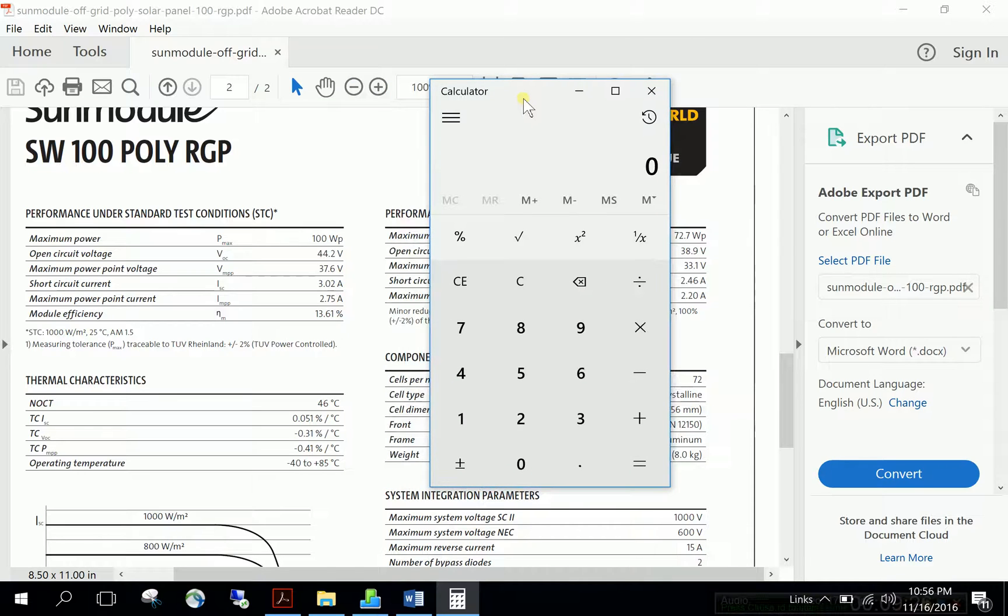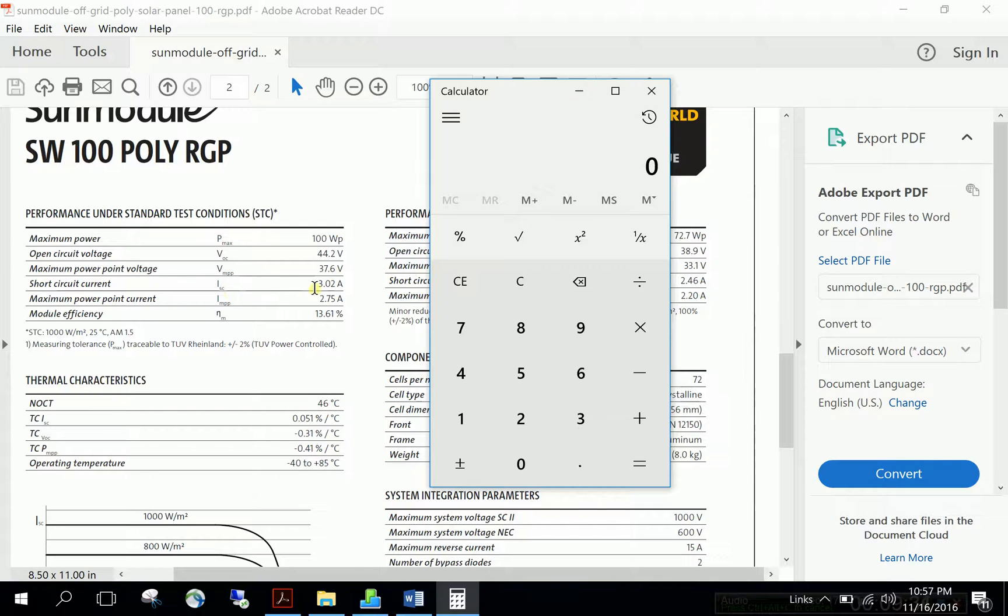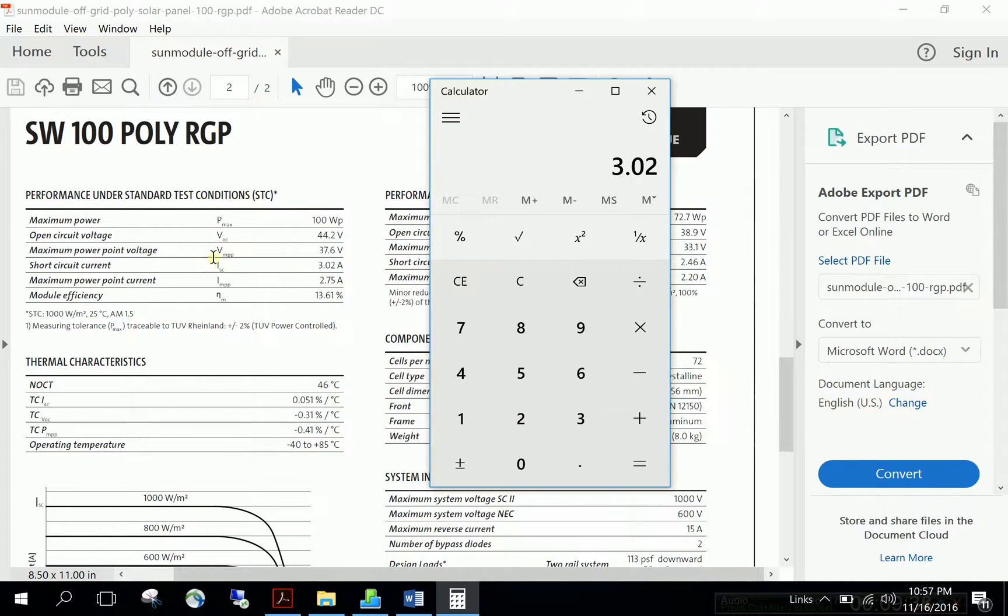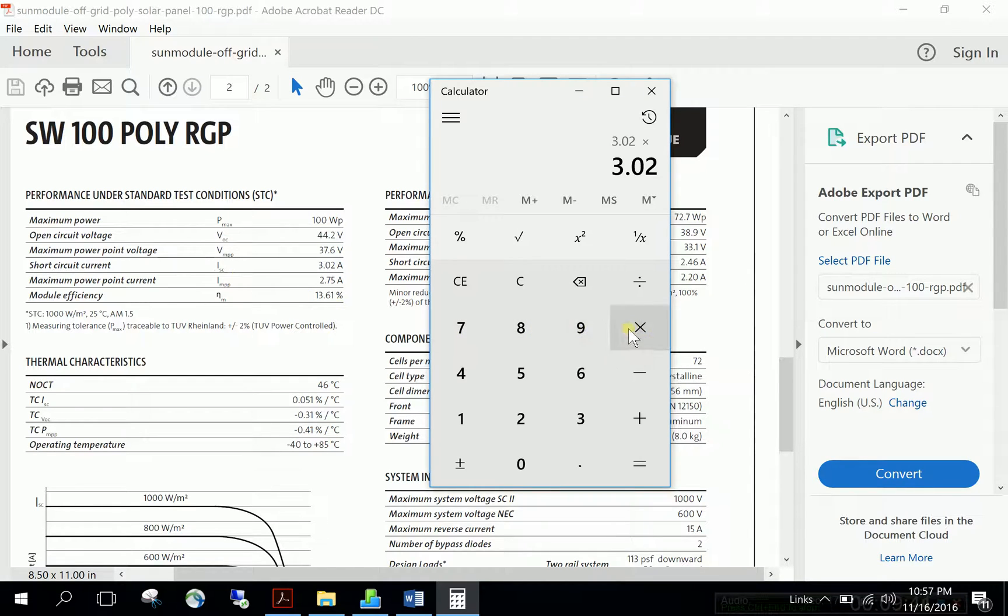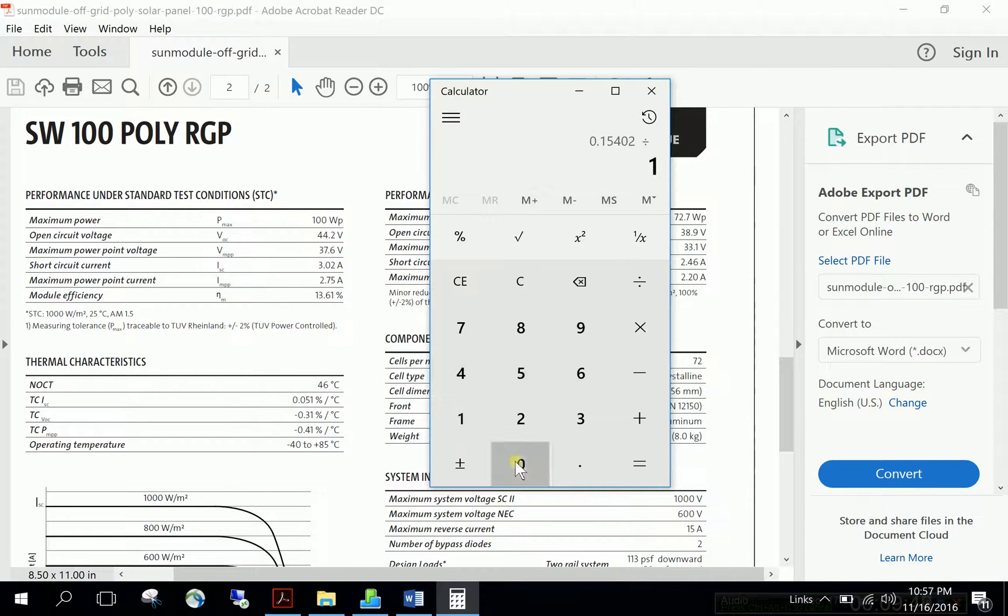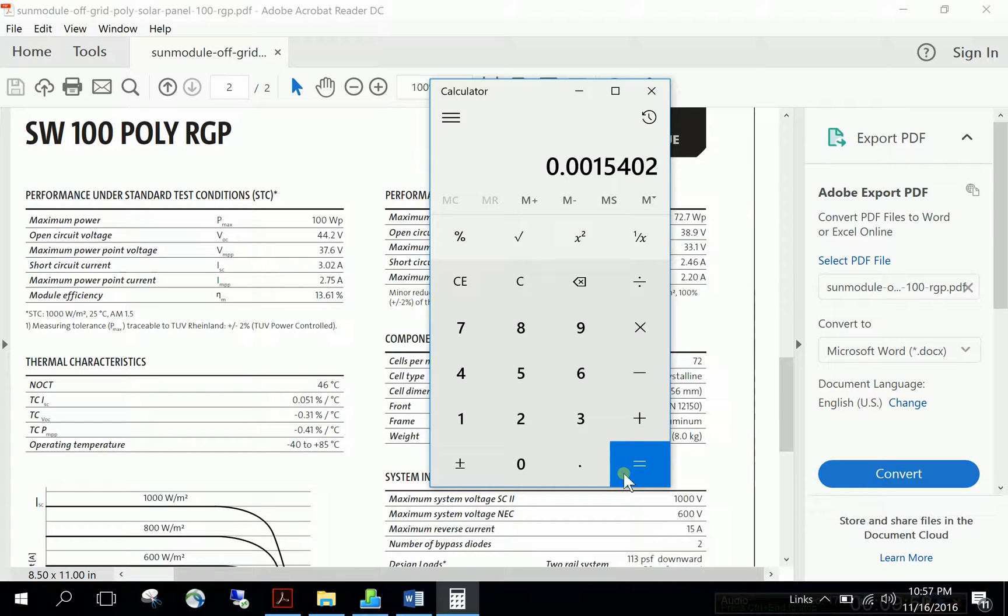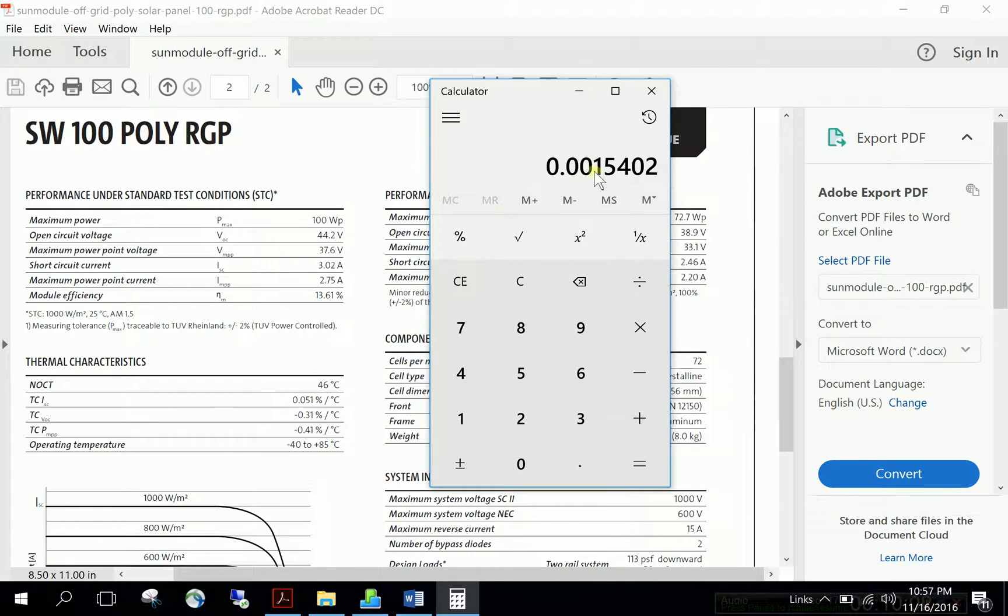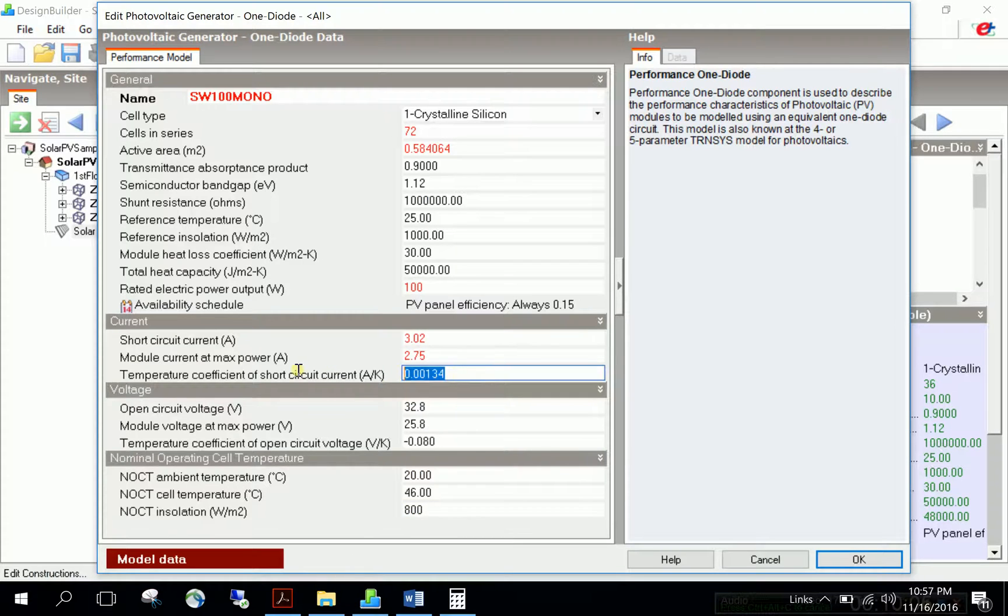To convert, find the short circuit current under standard test conditions, 3.02, multiply by the percentage value 0.051, then divide by 100 to get the amp per kelvin metric. Copy this result and provide it to the temperature coefficient input.